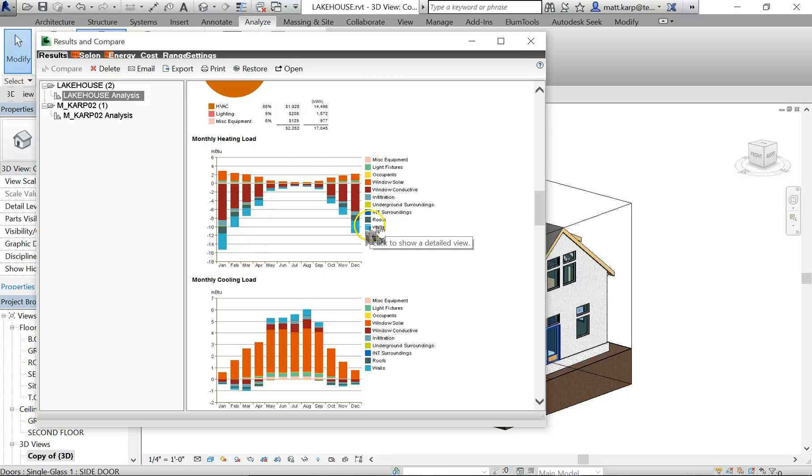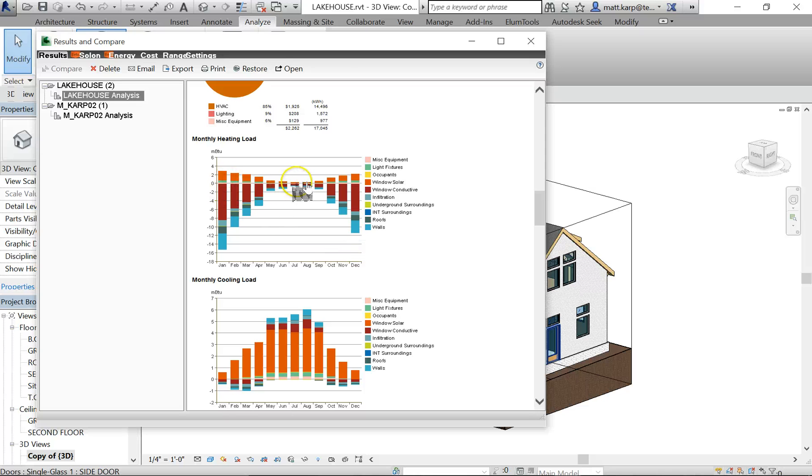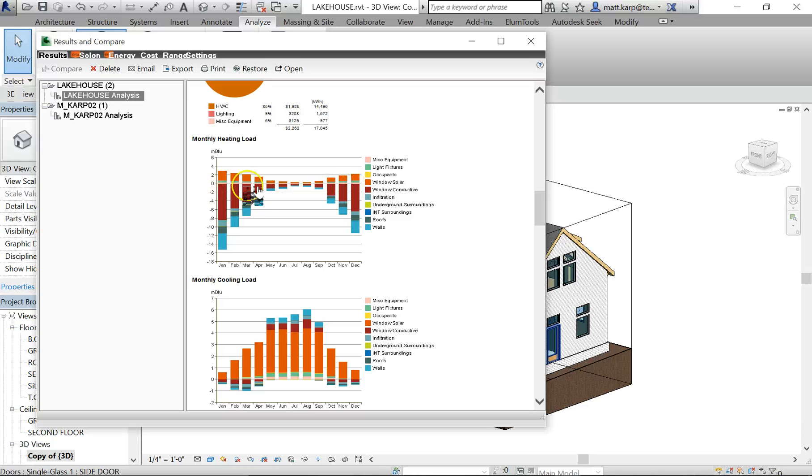This is showing how your heating load is working. Where are we losing pieces? A lot of it's going out through the window. We're gaining some heat from the window solar - that's why it's going positive in the BTUs there. Probably gaining a sliver of heat from occupants and lights, but then we're losing a lot of heat through our windows, so our windows aren't doing so great. And some heat through our walls.